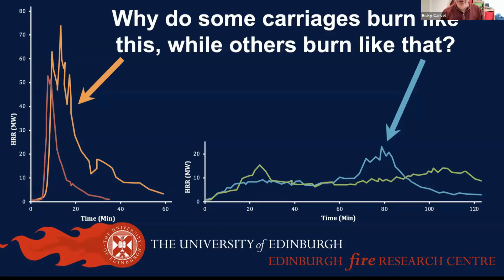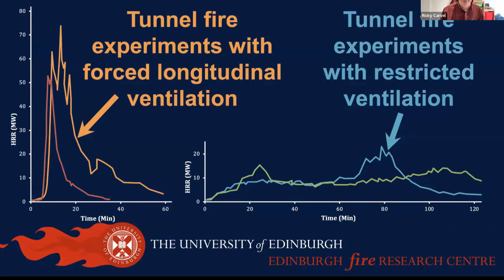And the answer is simple. The ones on the left were in experiments where we had the ventilation switched on, and the ones on the right were in experiments where the ventilation system was not switched on - in fact, measures were put in place to reduce the longitudinal flow. In other words, what we do with a ventilation system during a tunnel fire affects the dynamics of the fire. This should not be a surprise to anyone - blowing on a fire changes the fire.